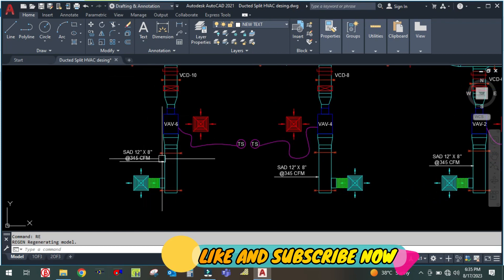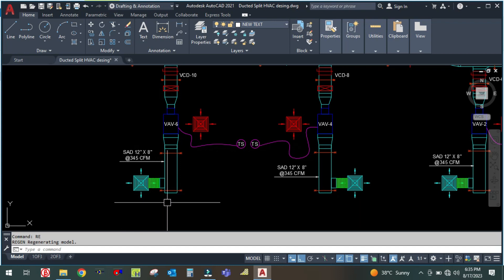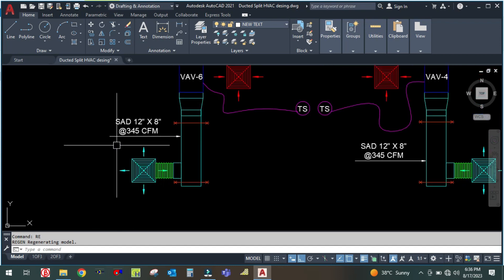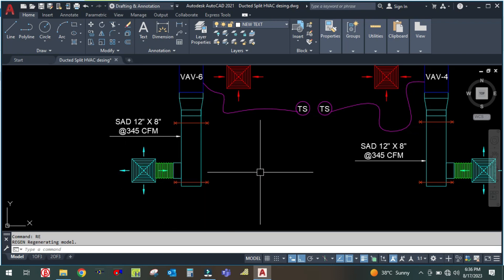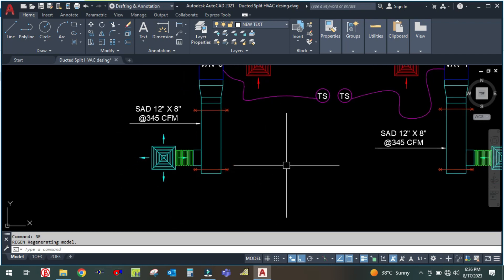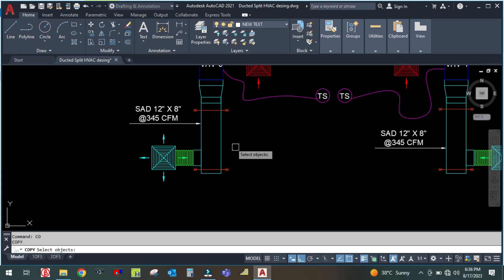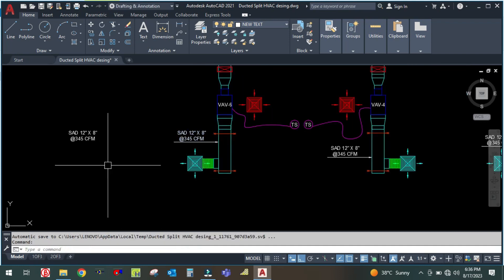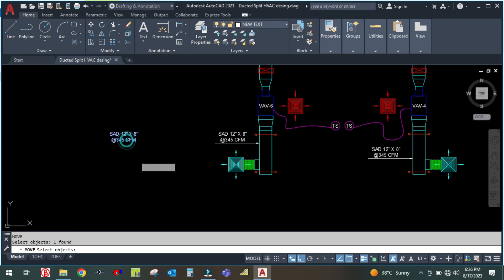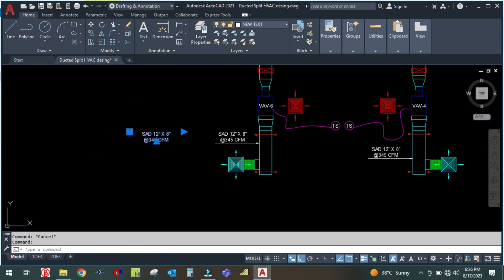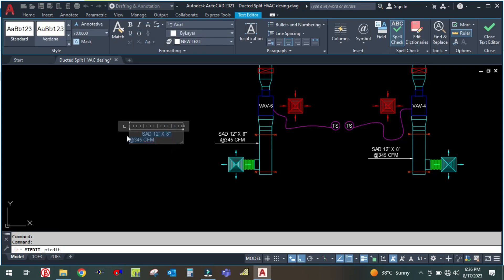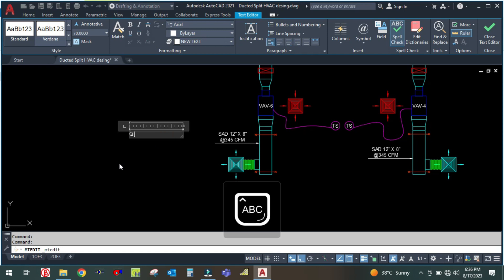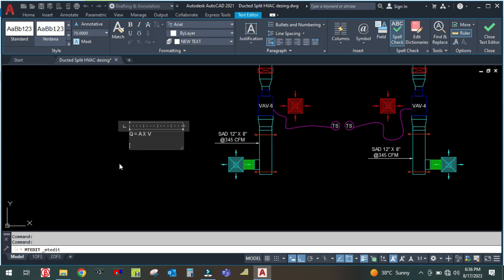That means this diffuser is also supplying 345 CFM only. There is one basic formula I will show you here. The total CFM for one diffuser: Q is equal to A into V.